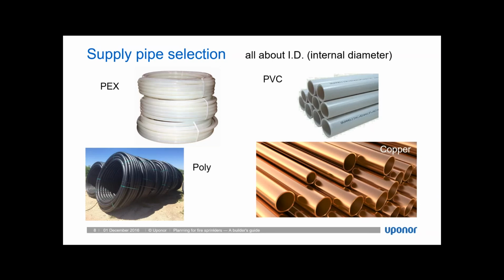And now I want to talk about the various supply piping that would be going between your city main and your meter, and then from the meter to the system riser in the home. It's important to note that all pipes are not created equal. These could all be 1 inch, and they would have different internal diameters.